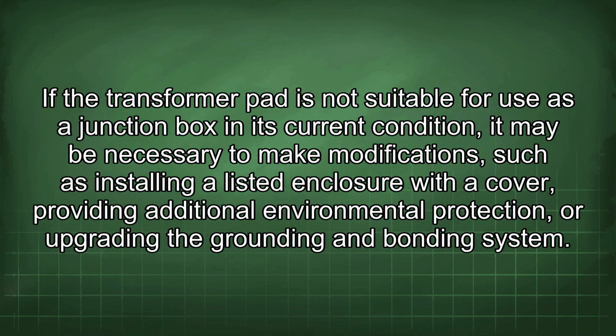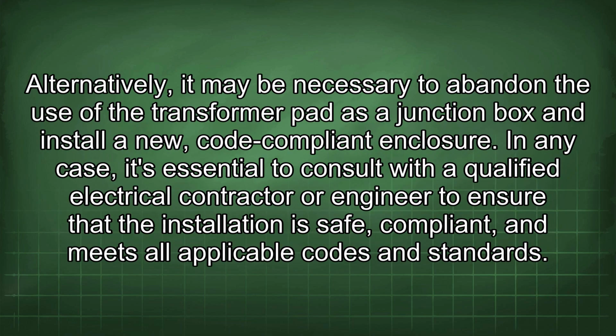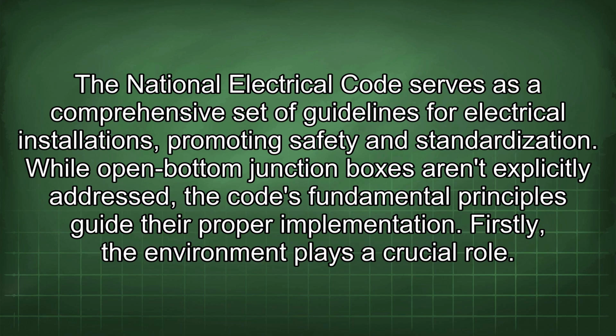If the transformer pad is not suitable for use as a junction box in its current condition, it may be necessary to make modifications such as installing a listed enclosure with a cover, providing additional environmental protection, or upgrading the grounding and bonding system. Alternatively, it may be necessary to abandon the use of the transformer pad as a junction box and install a new code-compliant enclosure. In any case, it's essential to consult with a qualified electrical contractor or engineer to ensure that the installation is safe, compliant, and meets all applicable codes and standards. The National Electrical Code serves as a comprehensive set of guidelines for electrical installations, promoting safety and standardization. While open-bottom junction boxes aren't explicitly addressed, the code's fundamental principles guide their proper implementation. Firstly, the environment plays a crucial role.